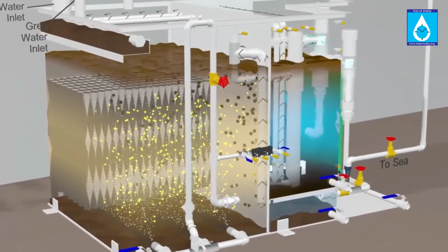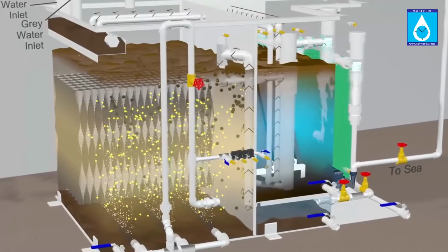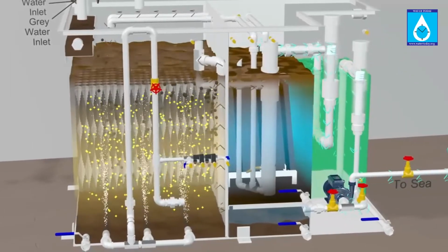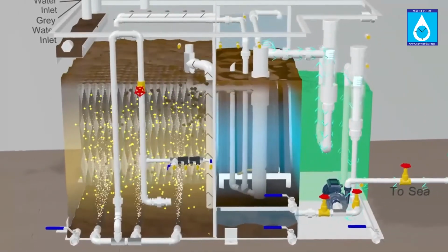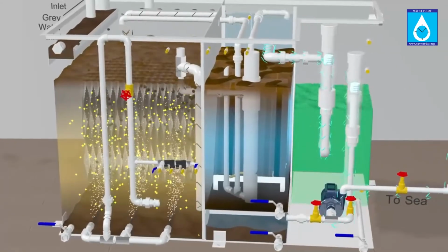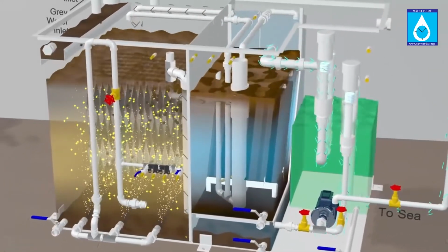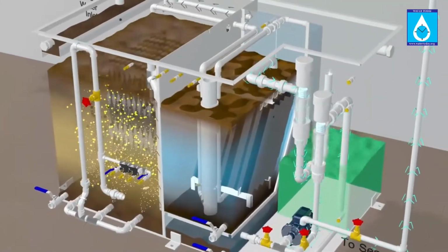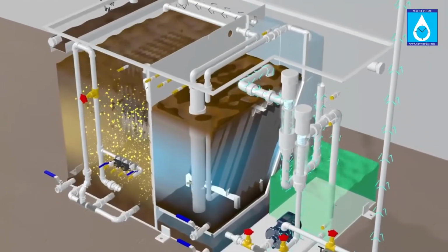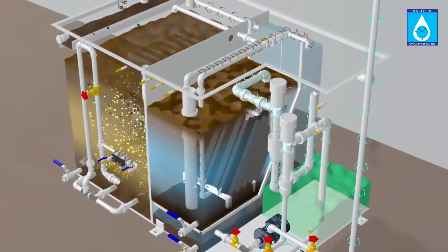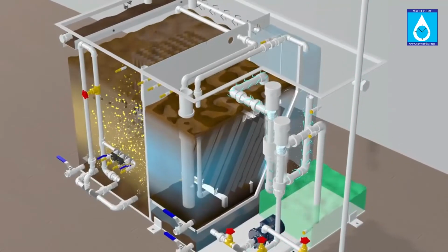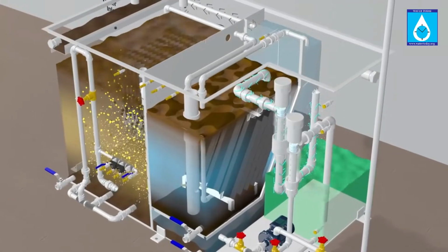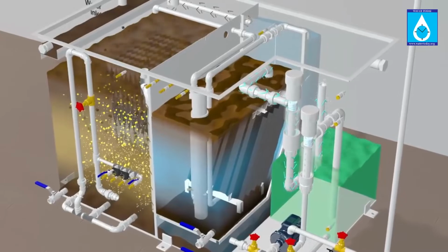And as we discussed in pressure boosting, we saw about building codes and where you can get the charts and discharge units and calculate how much peak demand you need to have. Exactly the same way, you can also do it for sewage. The thumb rule more predominantly is that if you give 100, 80 comes out as wastewater. So if you are pumping 100 liters of water, 80 liters will come back to you as effluent or sewage, or grey water, black water, whatever you call it. Then you need to do the treatment also according to that.